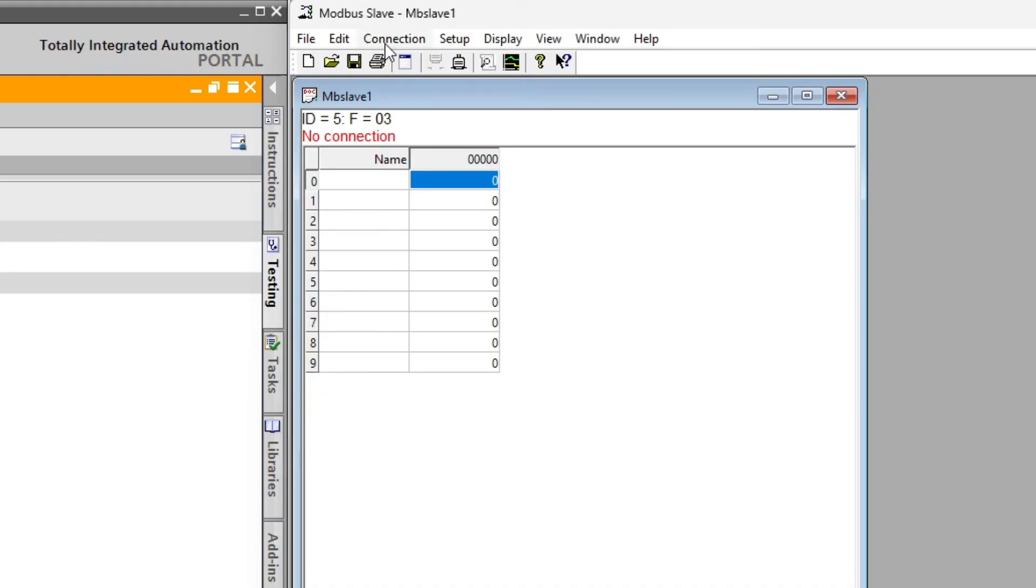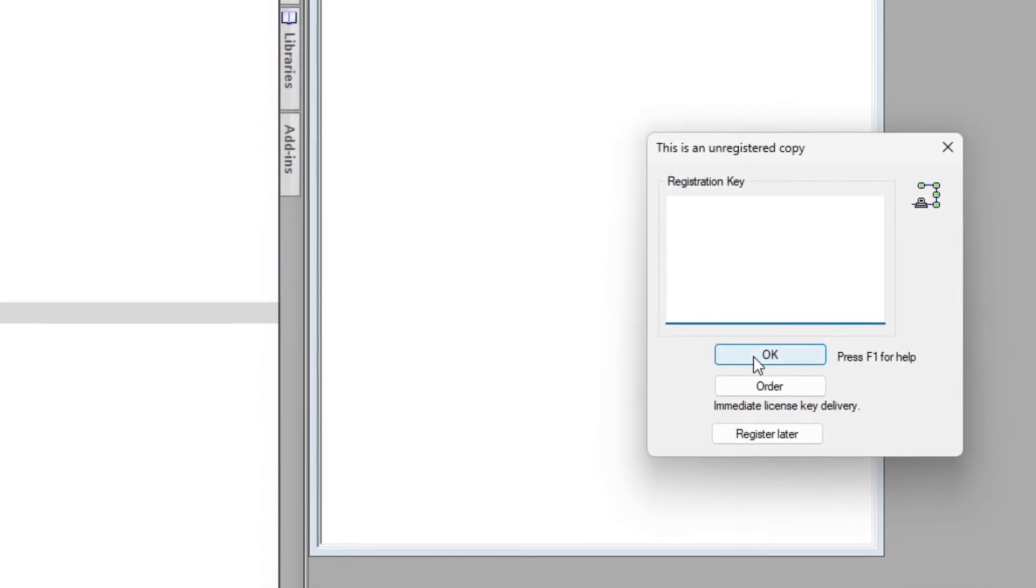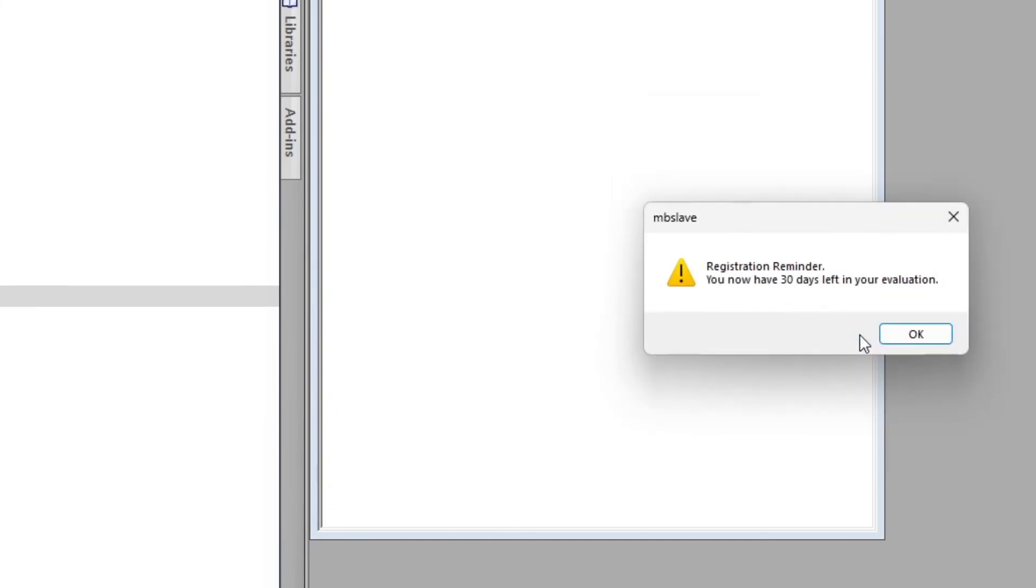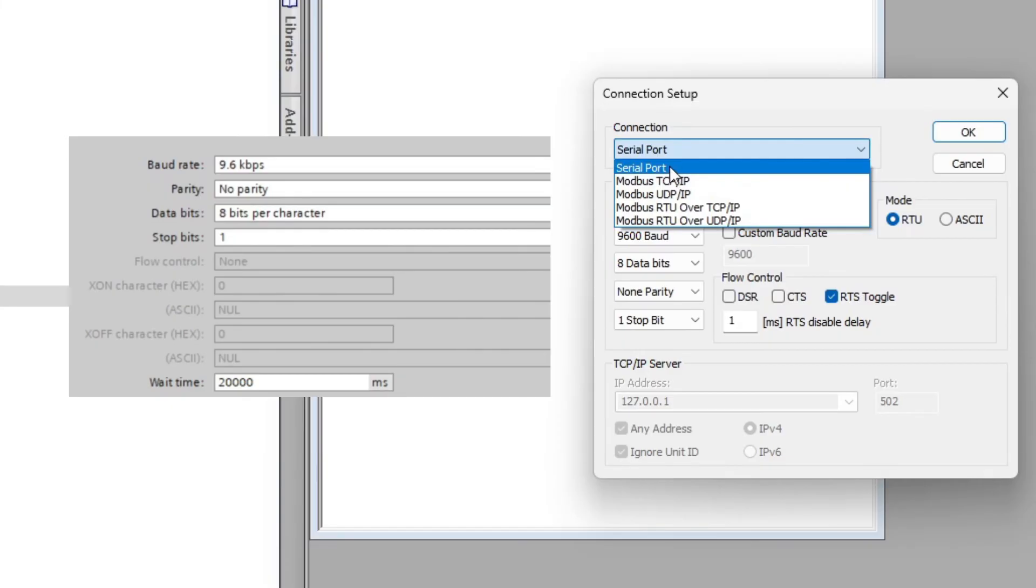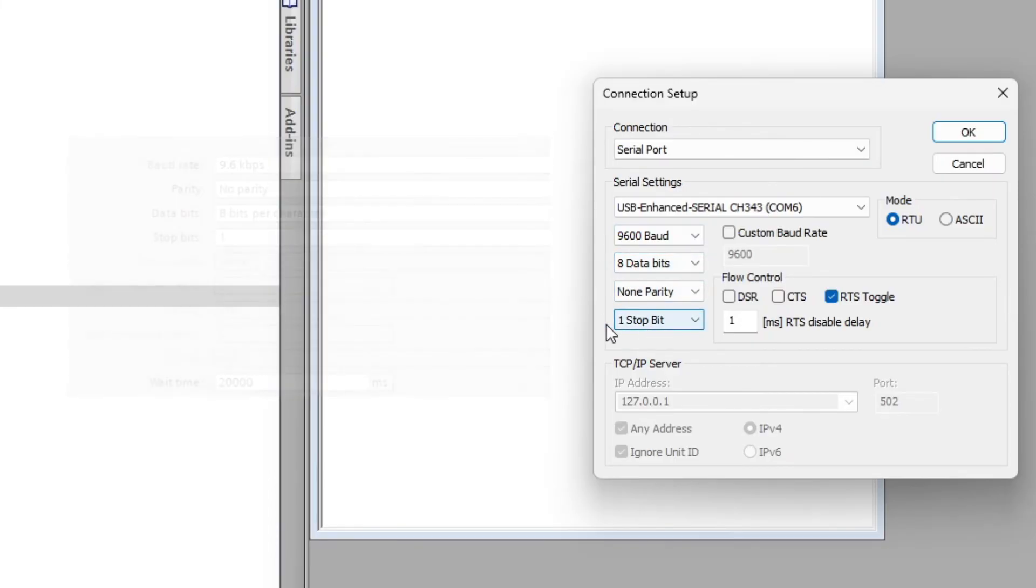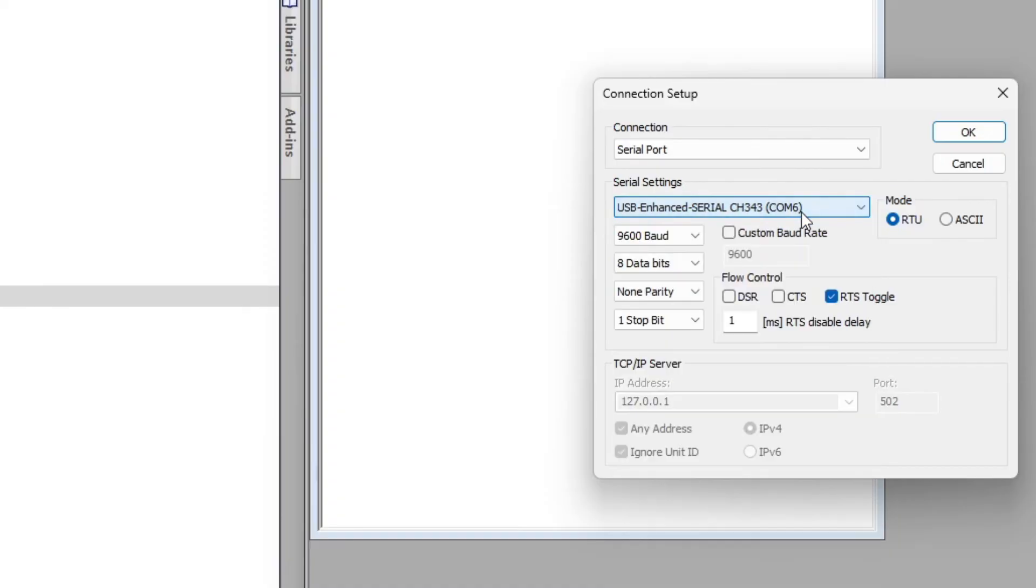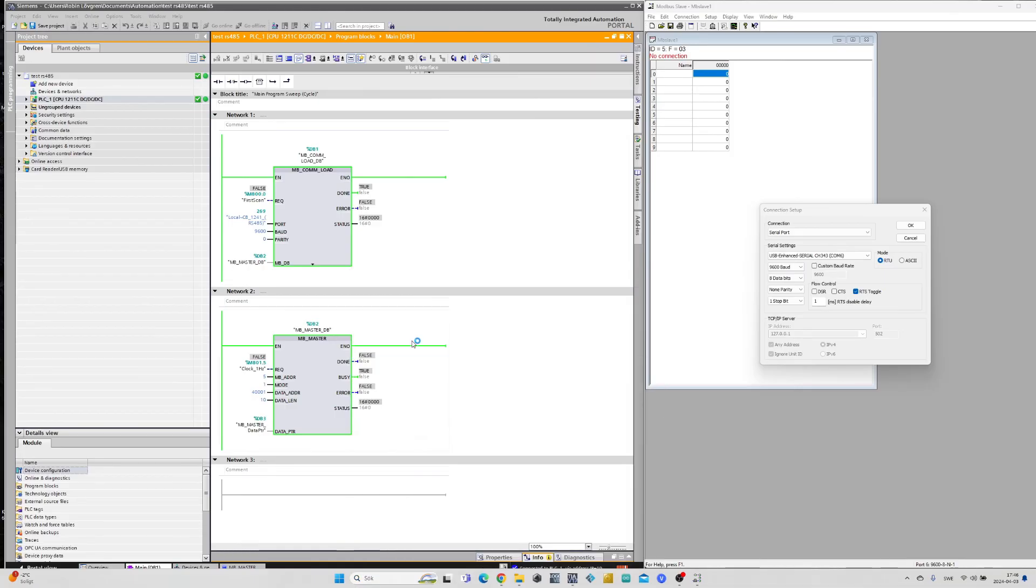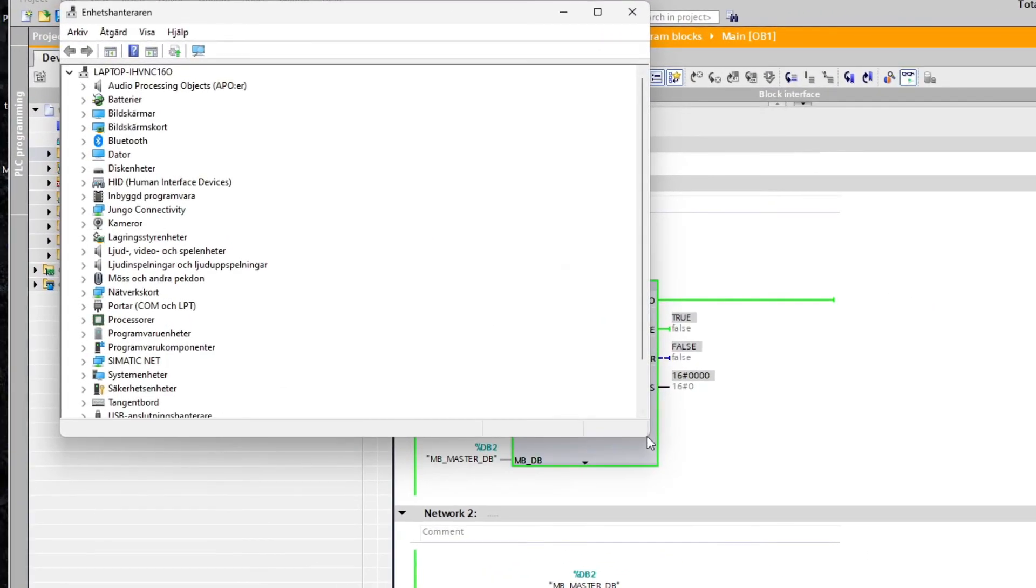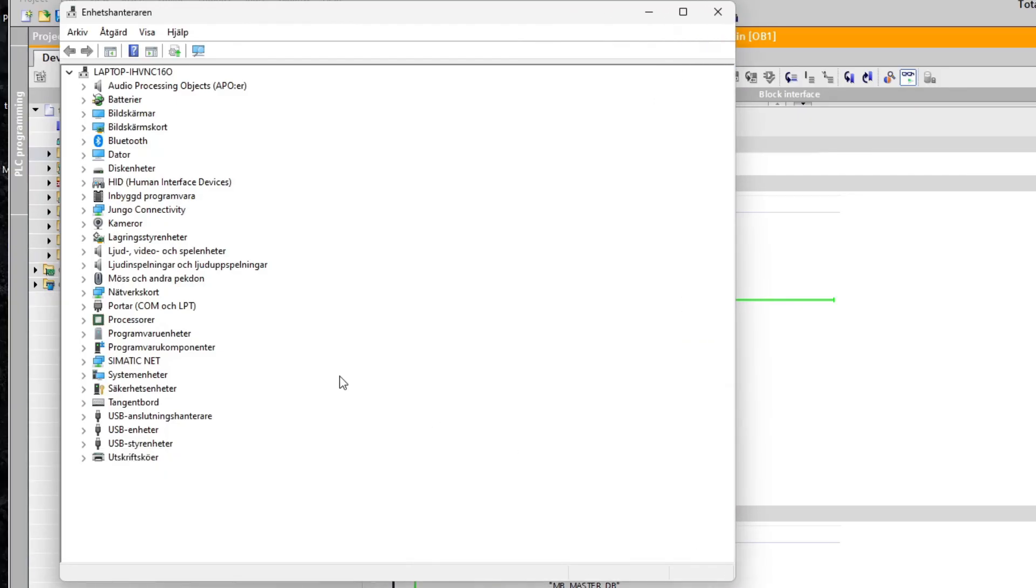We then want to go to connection and make a connection to the PLC. Here we want to make sure the connection setup match the settings from our RS-485 module. Then we also want to choose which COM port the USB is connected to. To find which COM port we're connected to we want to open up Device Manager. And under the COM and LPT tab we can find where our USB is connected.